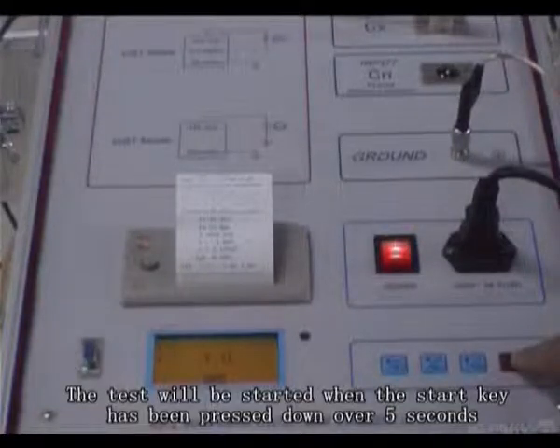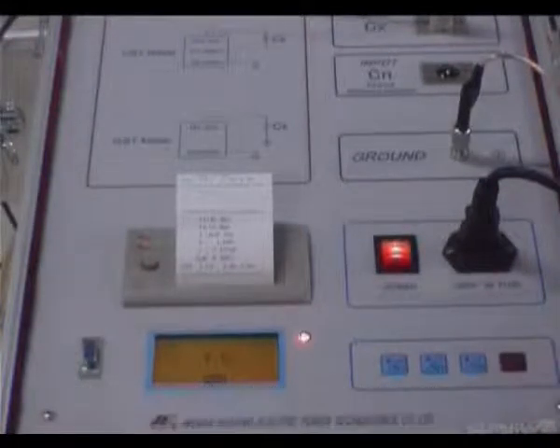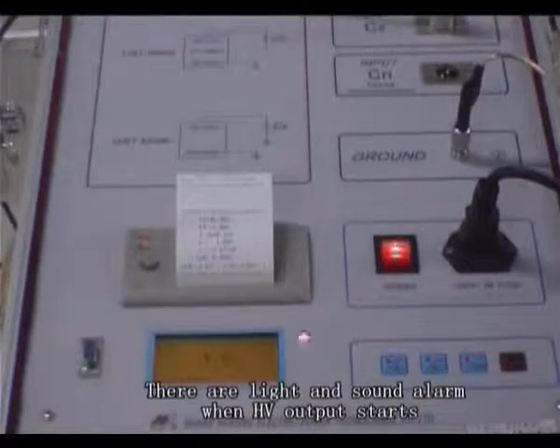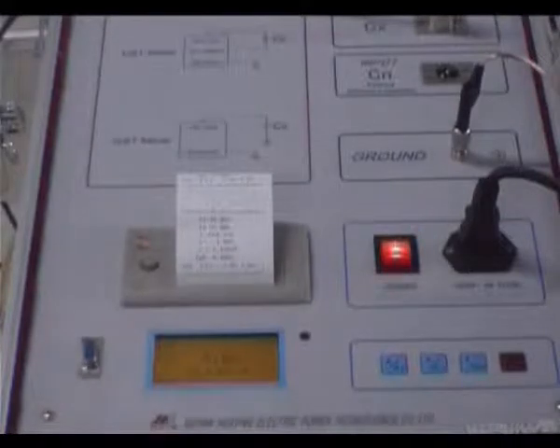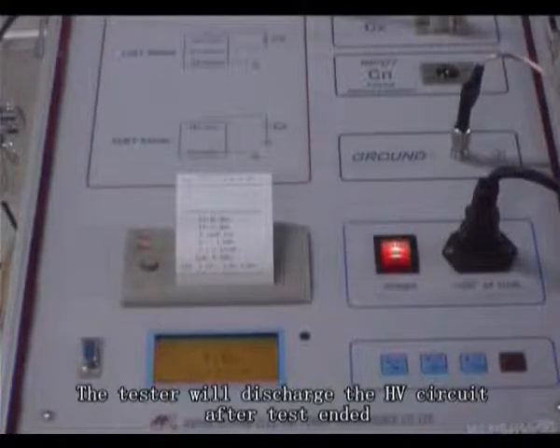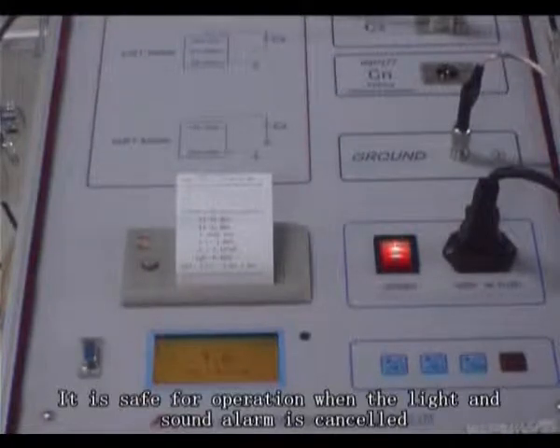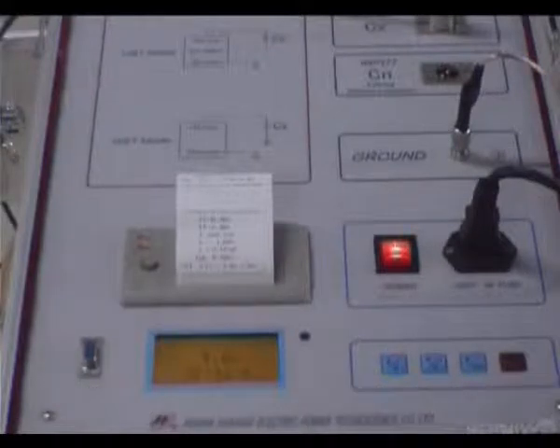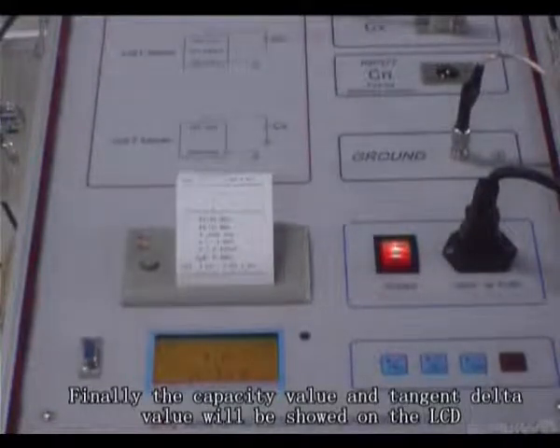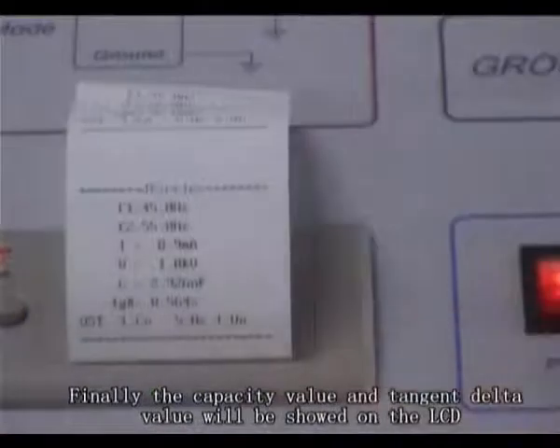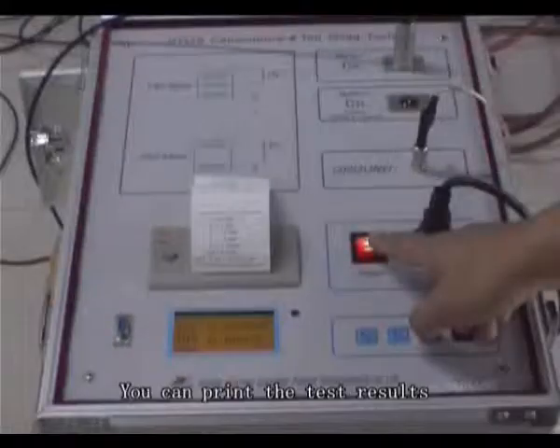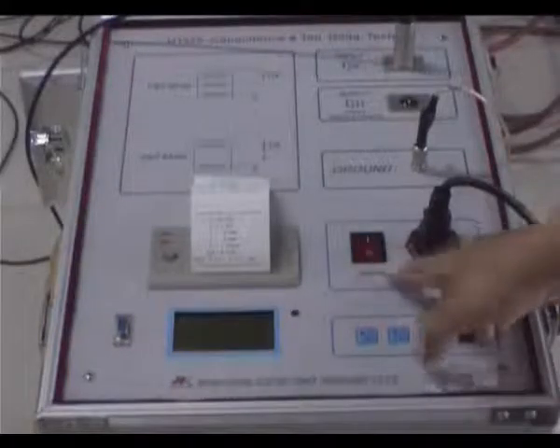The test will be started when the start key has been pressed down over 5 seconds. There are light and sound alarms when HV output starts. The tester will discharge the HV circuit after the test ended. It is safe for operation when the light and sound alarm is cancelled. Finally, the capacitive value and tangent delta value will be shown on the LCD. You can print the test results.